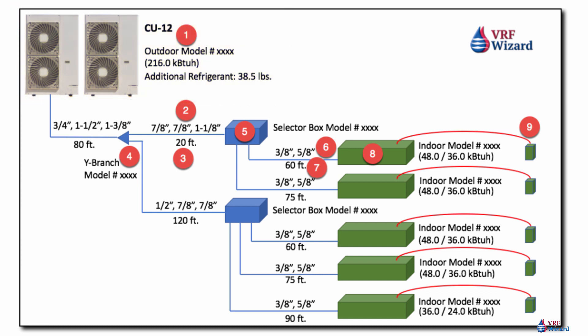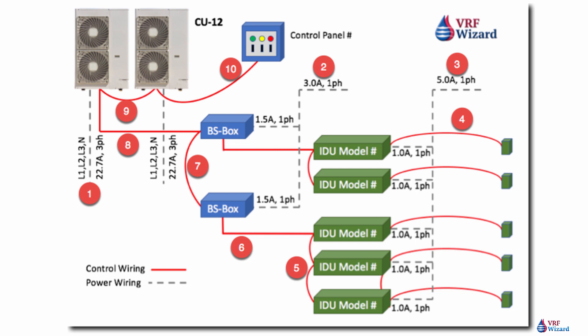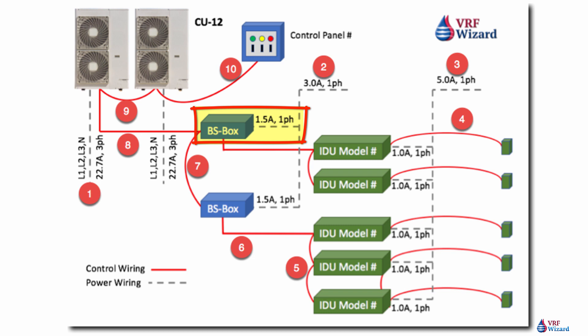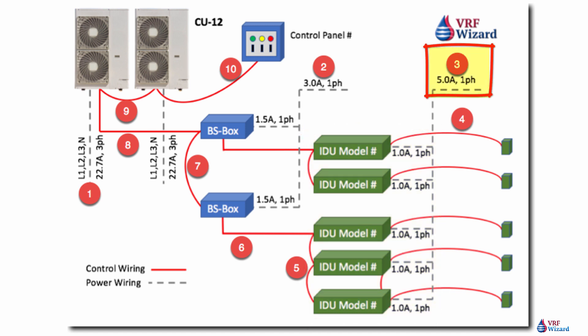You'll also have a VRF wiring diagram that will be automatically calculated and shown for you. It tells you the amps required — for example, 22.7 amps, three phase. It will tell you the power required to the branch selector box and the amps. It shows the same for the indoor units — for example, one amp single phase — and adds them all up to give you the total load, such as five amps single phase.